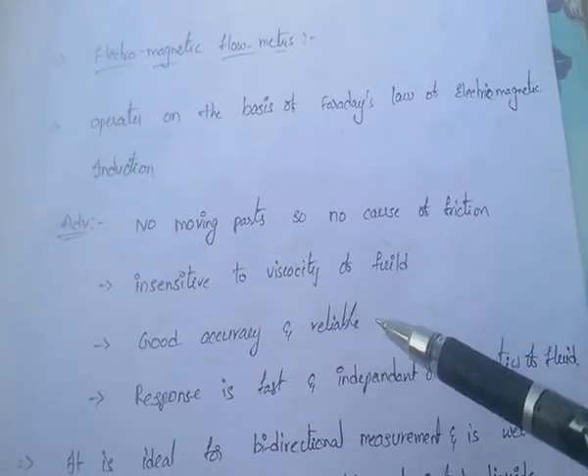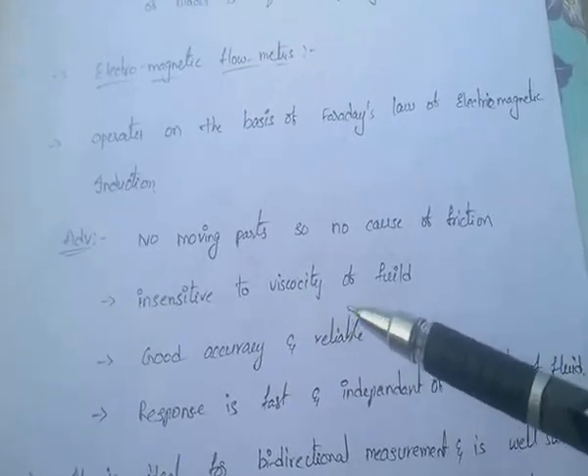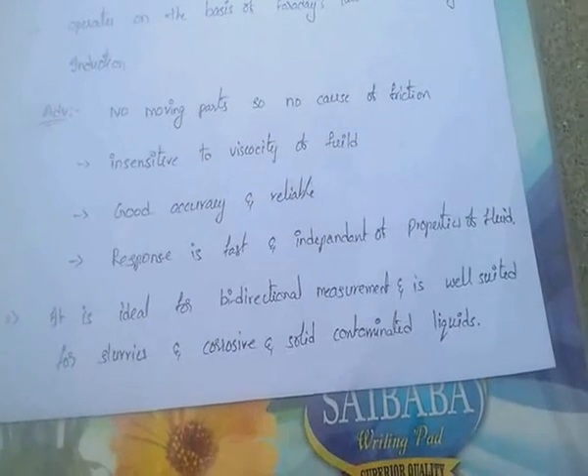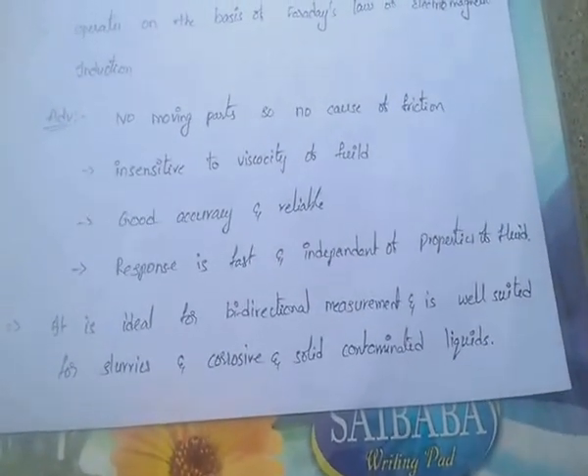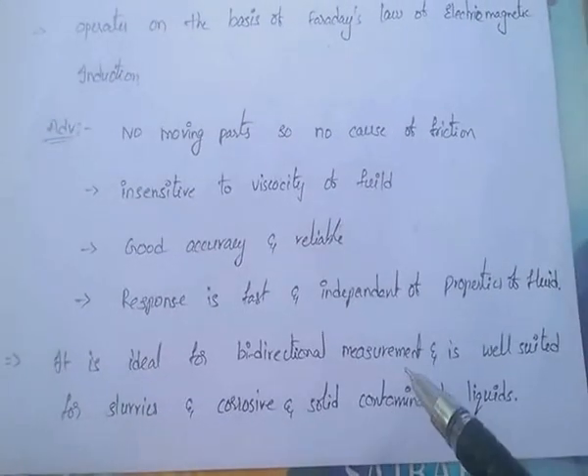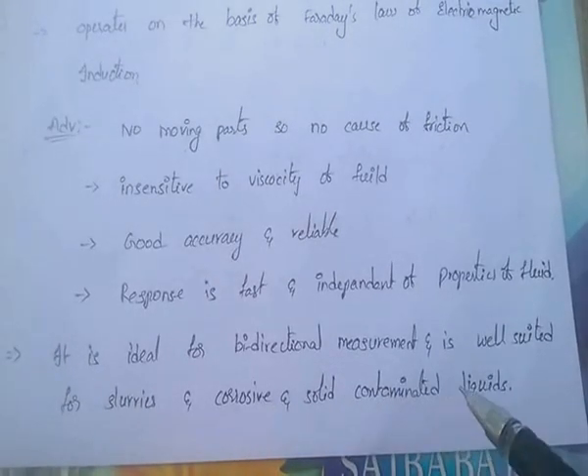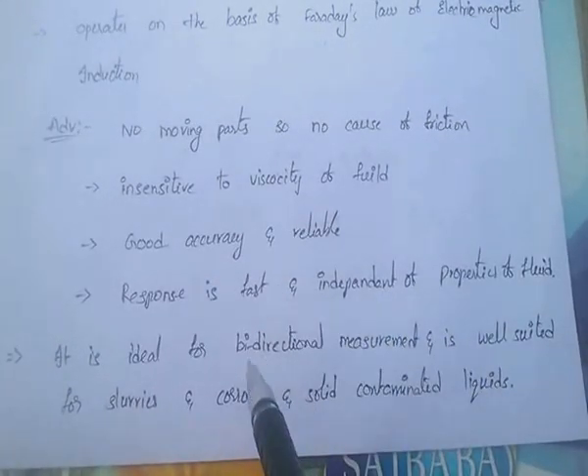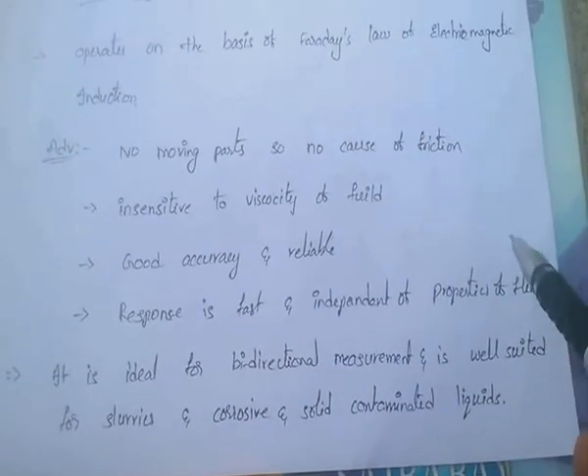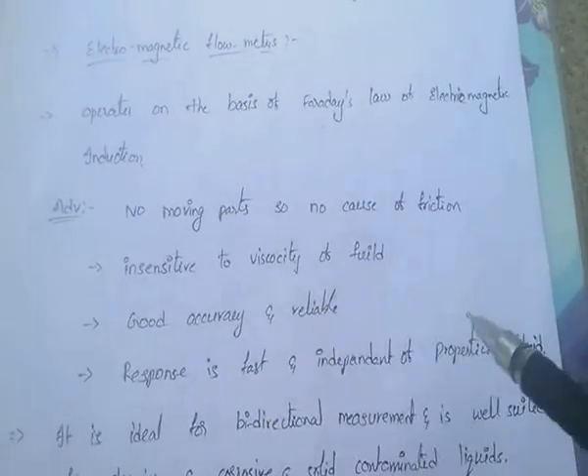Electromagnetic flow meters have good accuracy and are very reliable with a fast response. They are independent of the properties of the fluid. They are ideal for bi-directional measurement — whether the fluid flows in one direction or the other, it can be easily measured. They are also well-suited for slurries, corrosive, and solid-contaminated liquids.